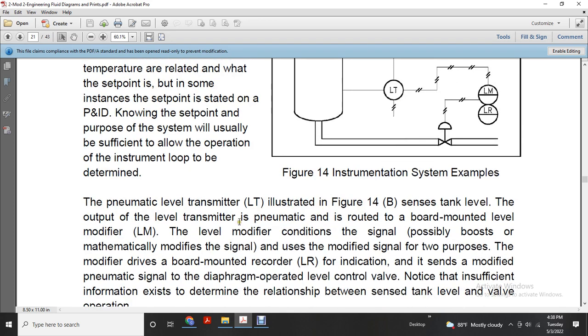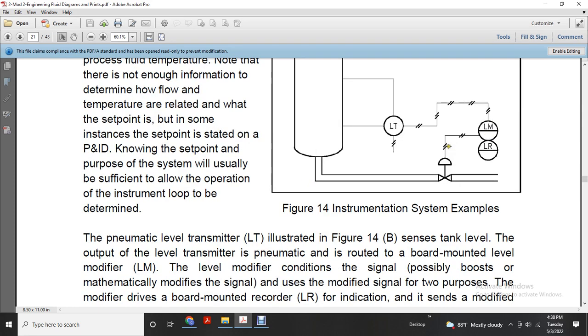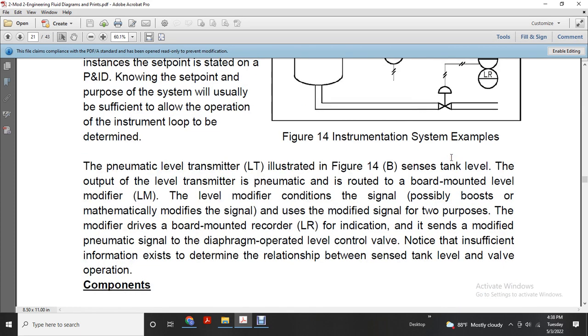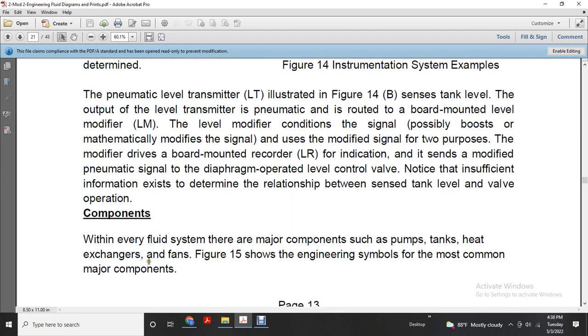The output of the level transmitter, the level modifier, recorder, and gate valves: the pneumatic level transmitter illustrated in Figure 14 senses the tank level. The output of the level transmitter, a pneumatic signal, is routed to the board mounted level modifier, which conditions the signal, possibly boosts or mathematically modifies the signal. The modified signal serves two purposes: it drives the board mounted recorder with the indication, and it is sent as a modified pneumatic signal to the diaphragm operator of the level control valve. Note that there is insufficient information to determine the relationship between the tank level and the valve operation.